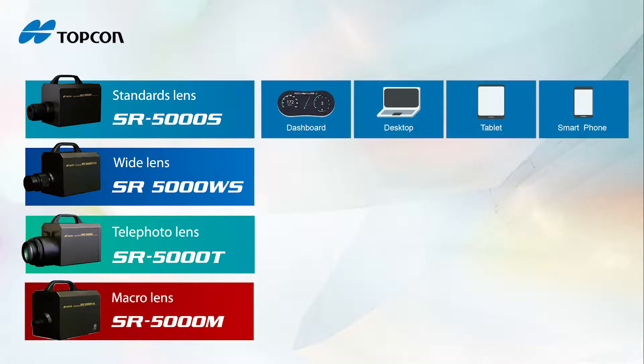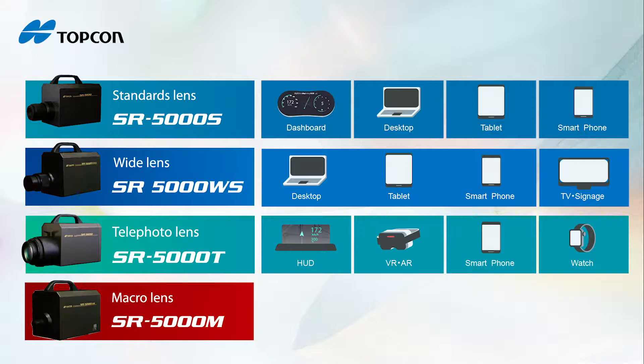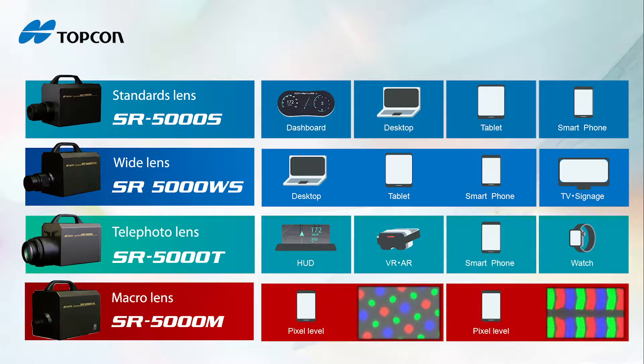Topcon Techno House designs lenses by ourselves, so we can provide SR 5000 series for different applications. The standard lens can measure dashboards, desktops, tablets, and smartphones. When you change to the wide angle lens, you can measure large size TVs. The Telephoto lens can measure VR devices, watches, and HUDs. For OLED or Micro-LED, you may need to understand the emitting characteristics of pixels — with Macro lens, you can get pixel-level information.